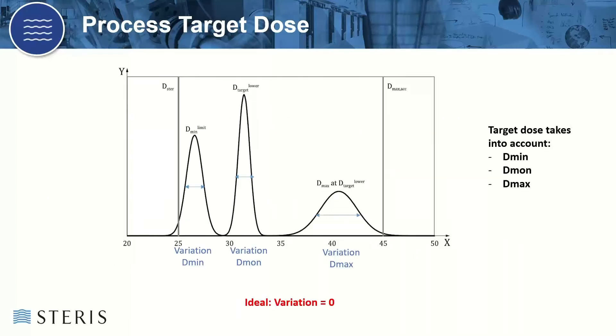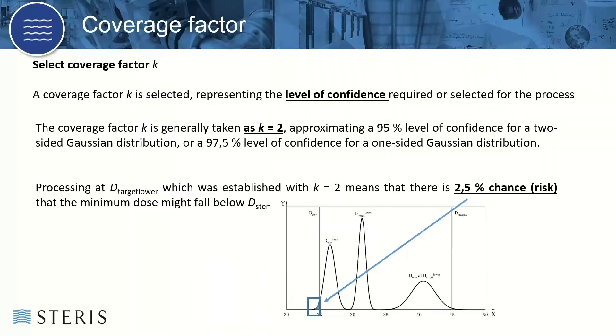This is a graphical representation of what we discussed. The target dose takes into account the minimum dose, the monitoring dose, and the maximum dose — all of which have variation associated with them and all need to be considered when setting process targets. A coverage factor K is selected representing the level of confidence for the process, usually K equals 2, which is a 95% confidence level for a two-sided Gaussian distribution or 97.5% for one-sided. For example, if processing at a lower target established with K equals 2, there is a 2.5% risk that the minimum dose might fall below the sterilization dose. So if you had a 25 kGy product specification and targeted 25 kGy, there is a 2.5% chance of falling below that level.